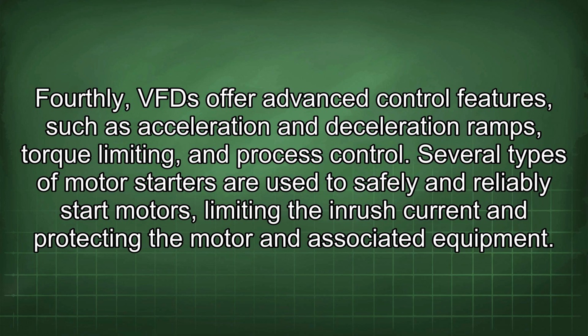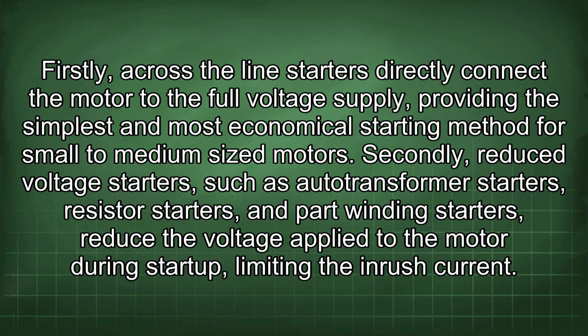Several types of motor starters are used to safely and reliably start motors, limiting the inrush current and protecting the motor and associated equipment. Firstly, across-the-line starters directly connect the motor to the full voltage supply, providing the simplest and most economical starting method for small to medium-sized motors.